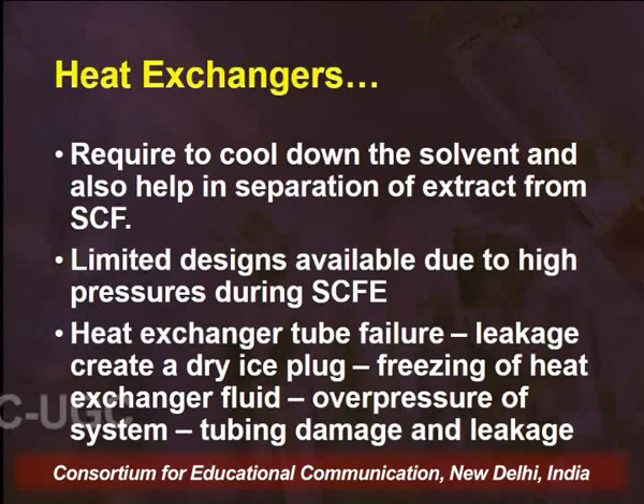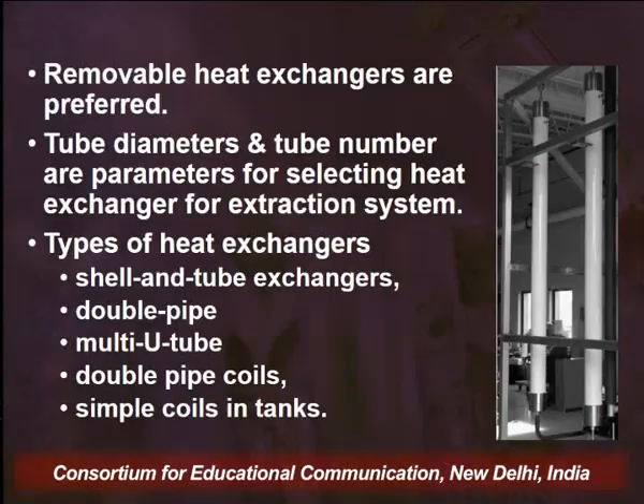And this overpressuring, as we discussed, may cause damage to the tubings, it may cause leakage from the seals or from the gasket, and once the pressure is increased, again the control system comes into the picture and it will shut down the whole system, thereby causing the loss in the form of the amount that is involved in raw material or the solvents. And therefore, by and large, removable heat exchangers are preferred. So if there is any kind of problem in one exchanger, it can be easily replaced by a new one or the already repaired one.